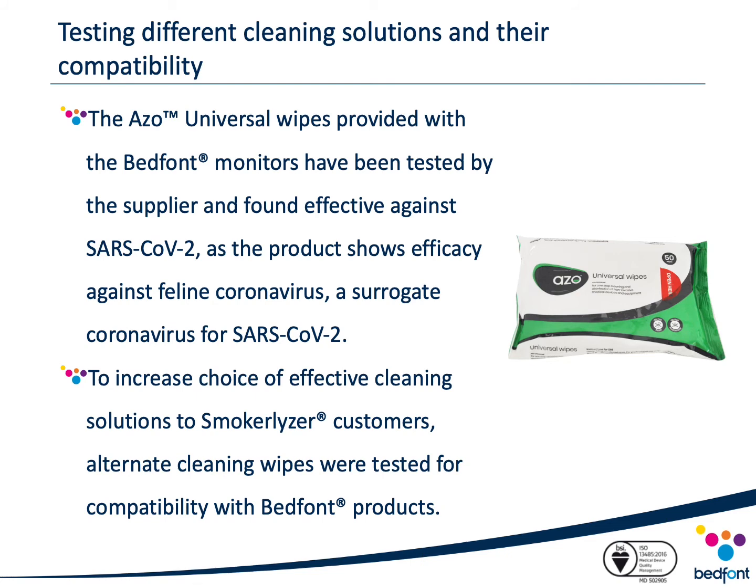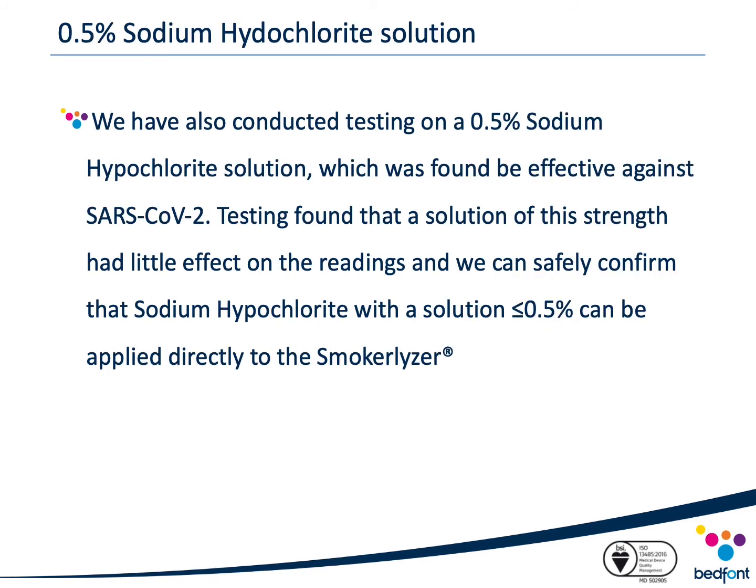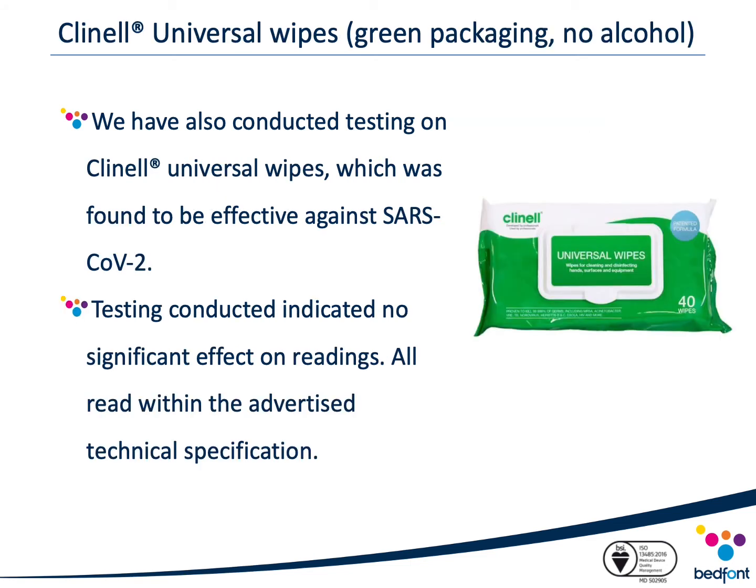Two alternative cleaning solutions were tested on our monitors. First, 0.5% sodium hypochlorite solution — found to be effective against COVID-19 and readily available in hospitals and clinics — was tested and found to have a negligible effect on CO readings, and therefore can be used to clean the external surfaces of our CO monitors. Next, Clinell universal wipes (non-alcoholic version), also effective against COVID-19 and readily available in hospitals, were likewise found to have a negligible effect on CO readings and can be used to clean external surfaces.